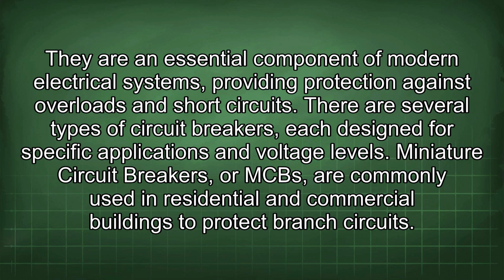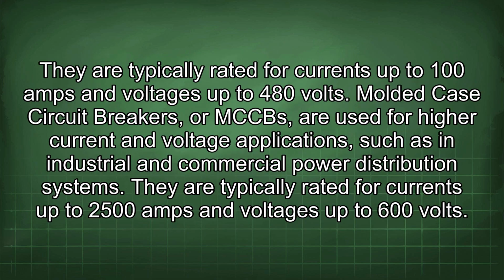There are several types of circuit breakers, each designed for specific applications and voltage levels. Miniature circuit breakers, or MCBs, are commonly used in residential and commercial buildings to protect branch circuits. They are typically rated for currents up to 100 amps and voltages up to 480 volts.